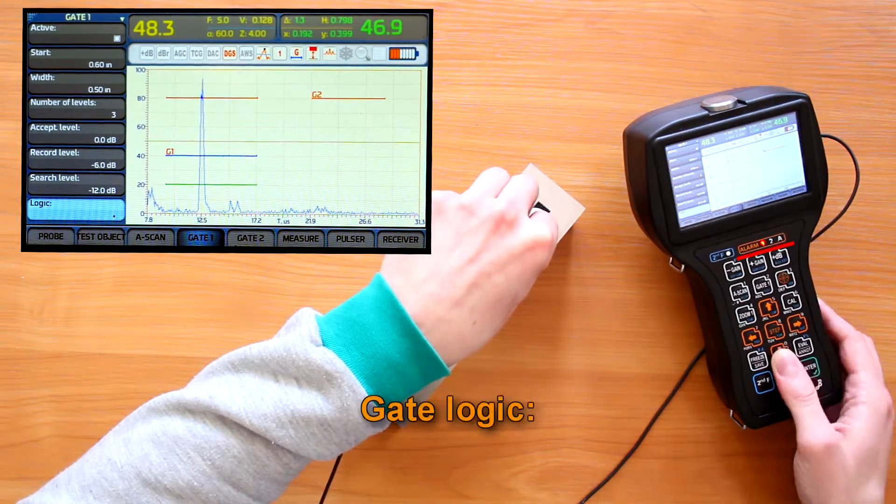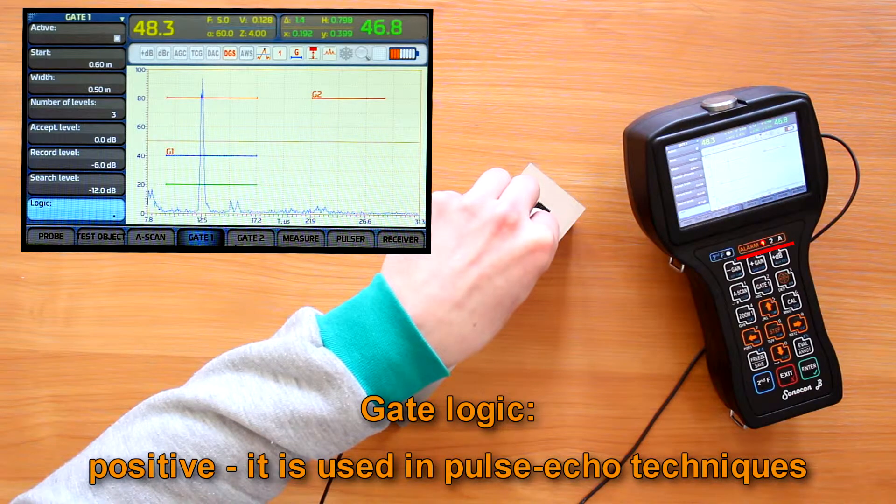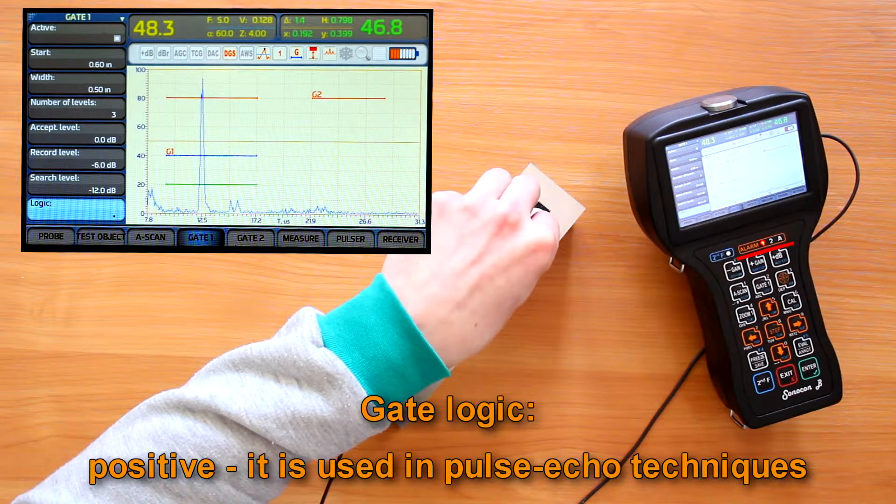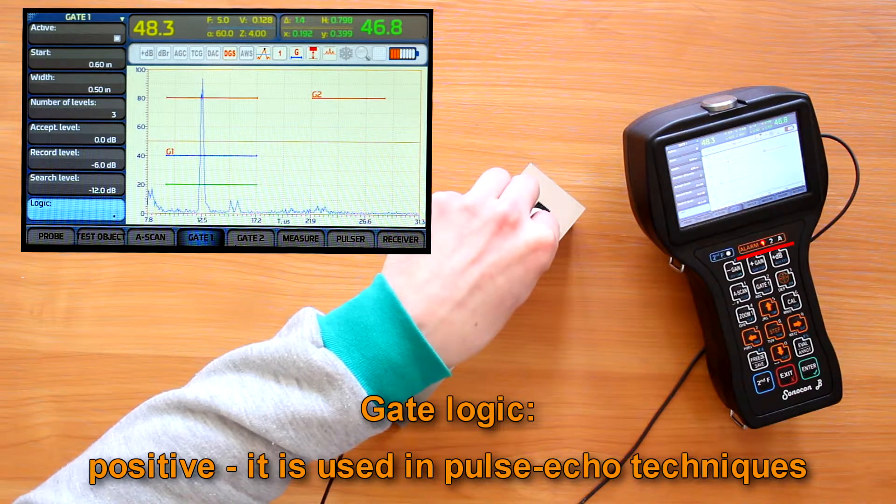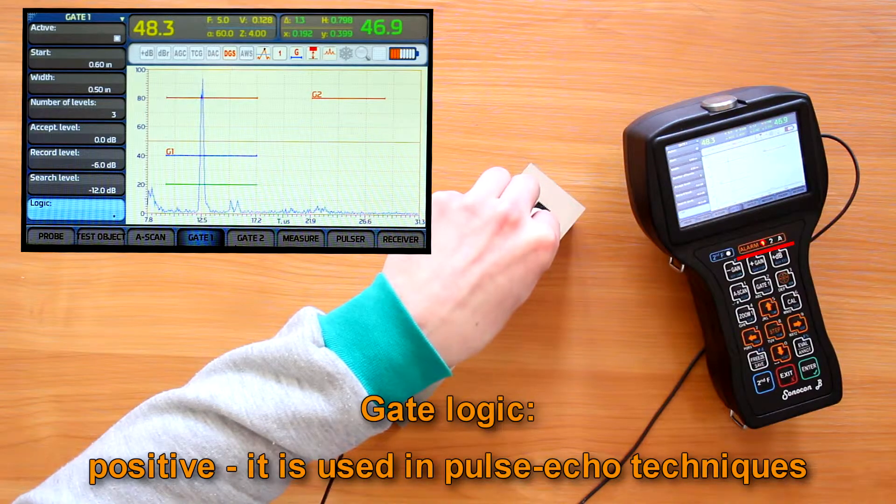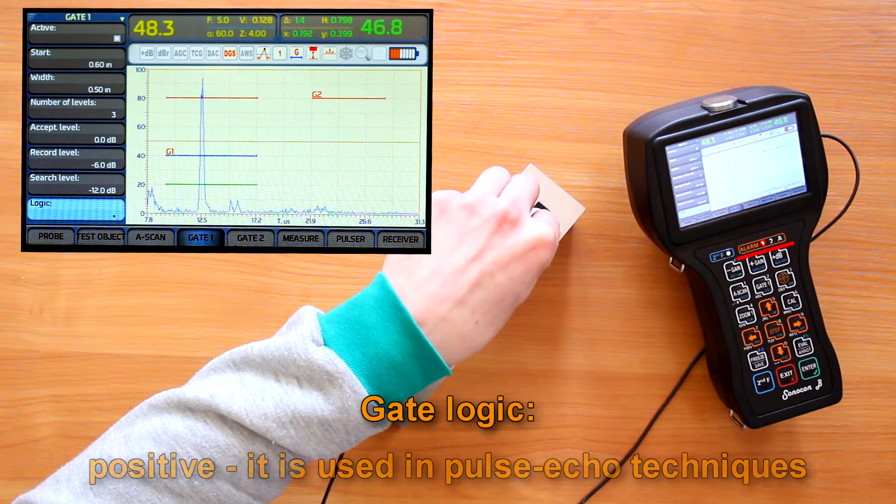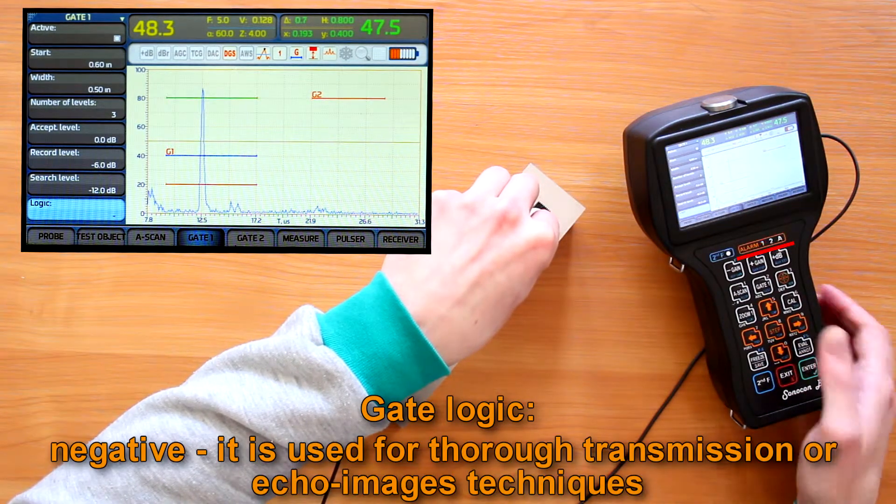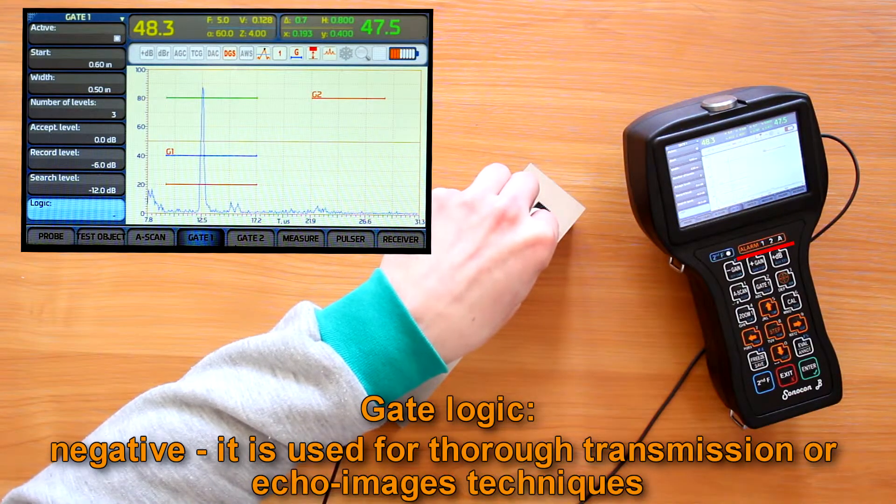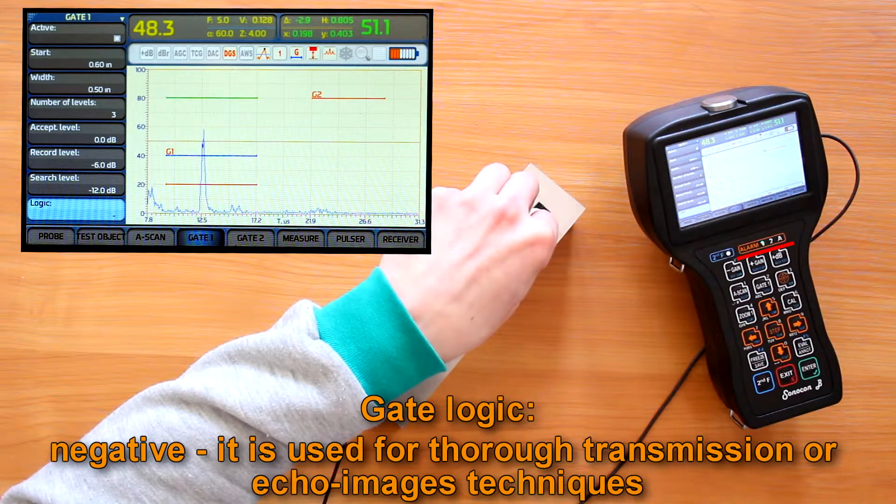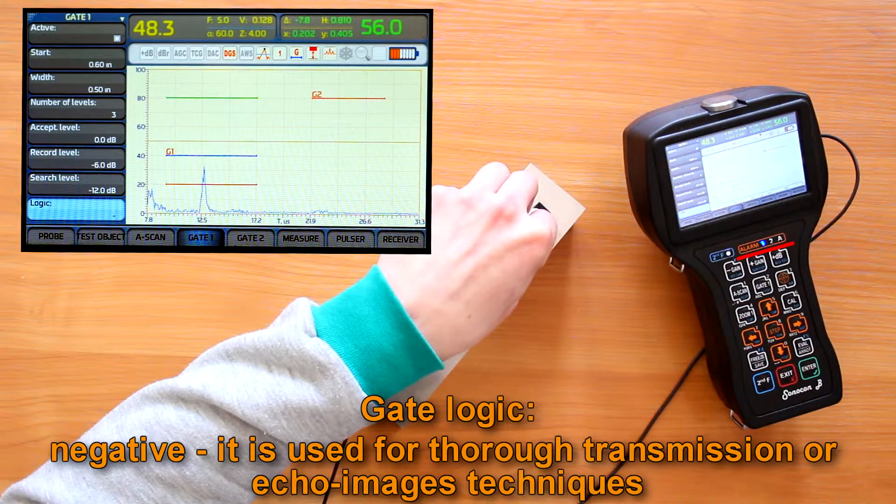Also, we can choose the gate logic. Positive. To alert about the indication detection when a signal exceeds the gate level. It is used in pulse echo techniques. Or negative. To alert when the reference signal falls below the gate level. It is used for through transmission or echo images techniques.